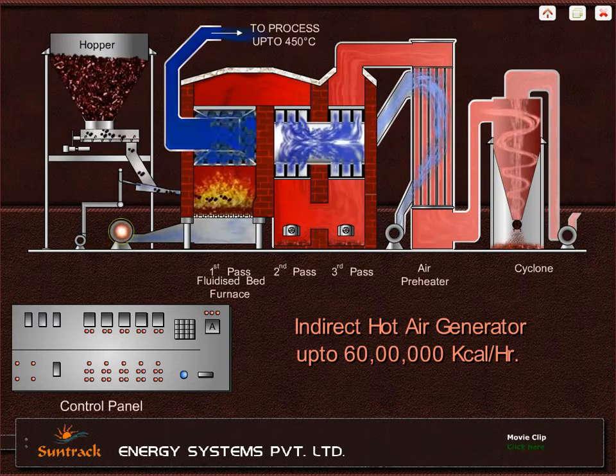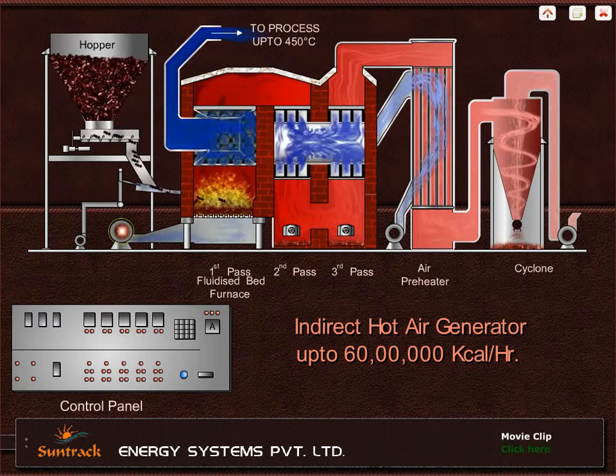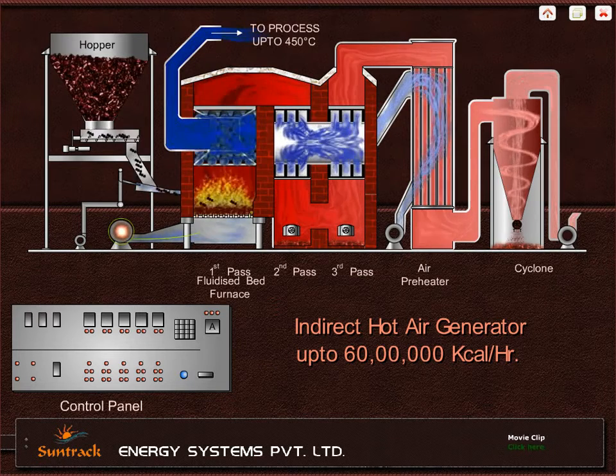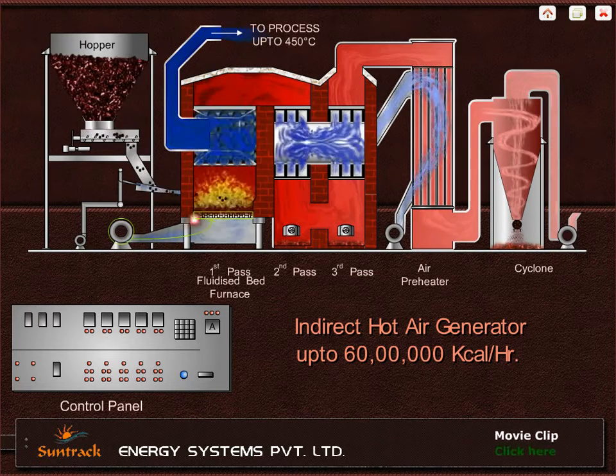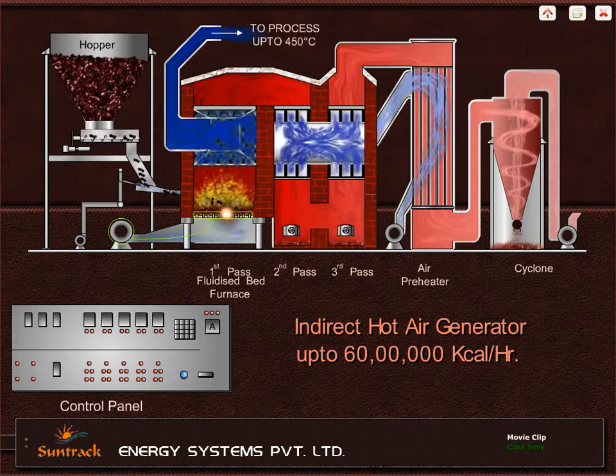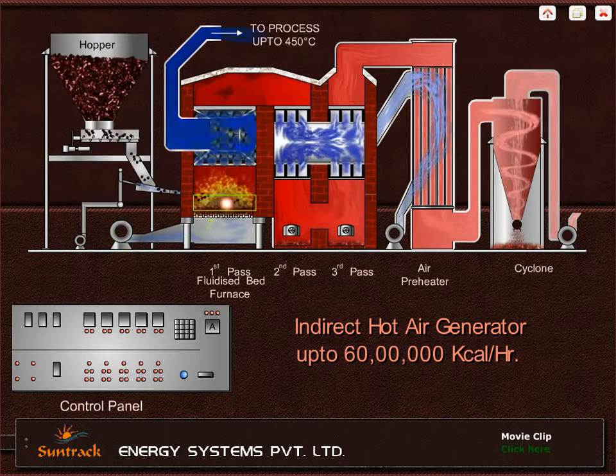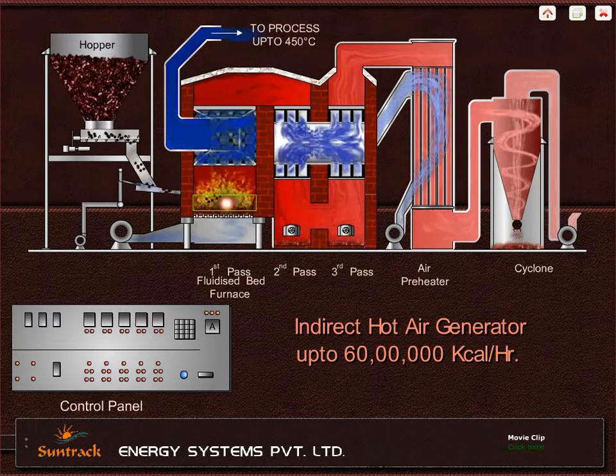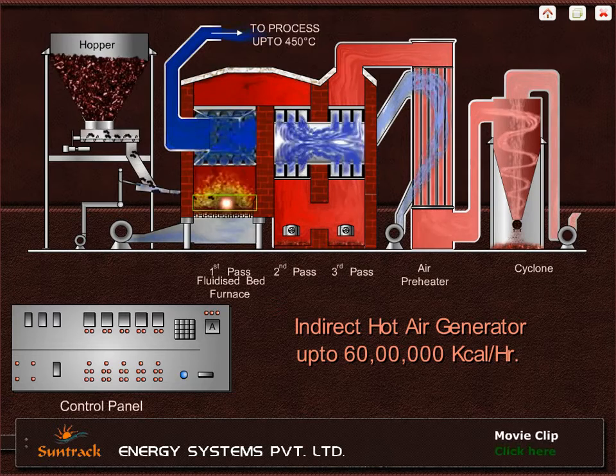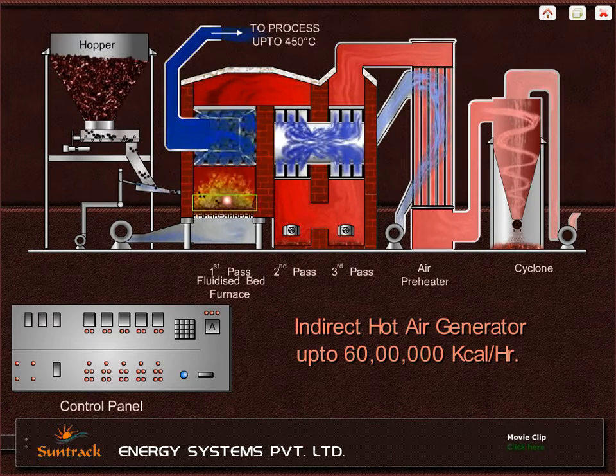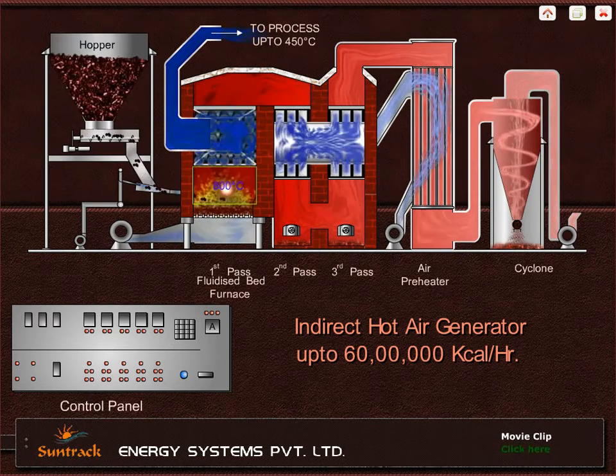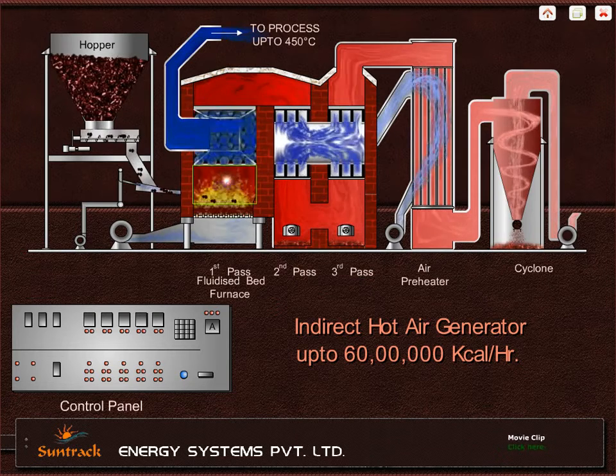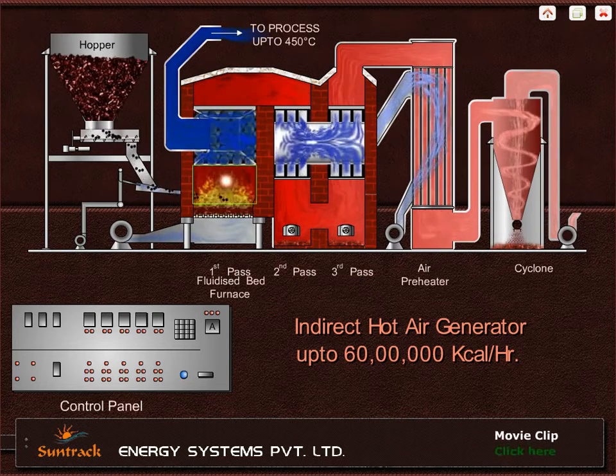Force-draught fan, or FD fan, installed in the system gives fluidization and combustion air to the fuel through specifically designed nozzles. The furnace has bed material which in most cases is river sand. Bed material remains under continuous fluidization and bed temperature maintained is about 800 degrees Celsius. Fuel falls on this hot bed and burns fully and instantly.